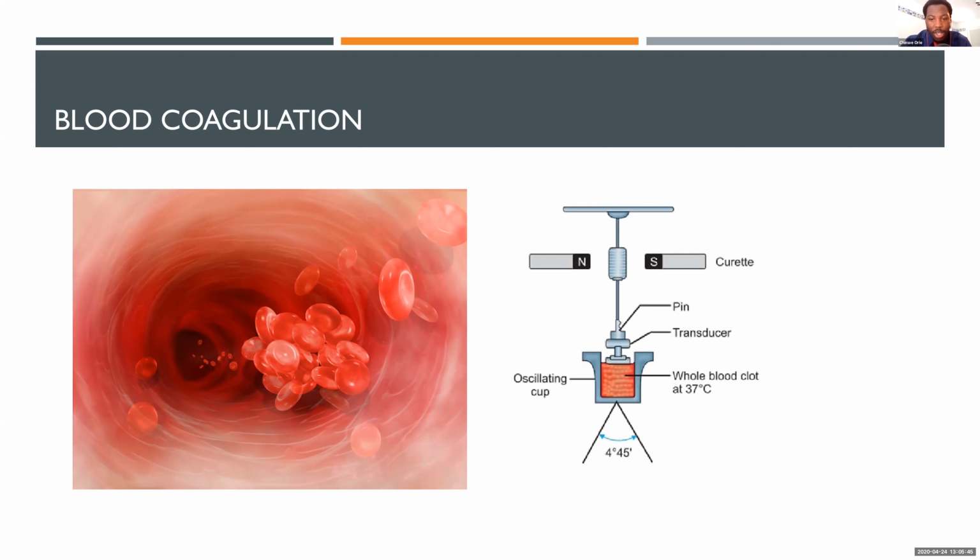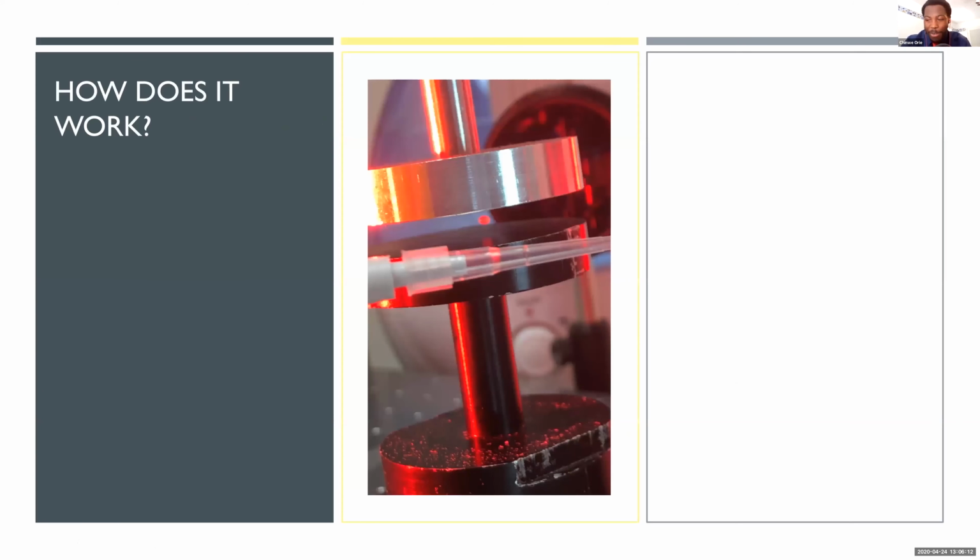It's the rotational thromboelastometer. But one of the main problems with such devices is that they require sample contact with the device. And that could lead to inaccurate measurements and unwanted chemical reactions that might alter measurements. So our lab has developed technology where we can use ultrasound to perform non-contact measurements to mitigate that kind of problem. And here's an example of levitated fluid.